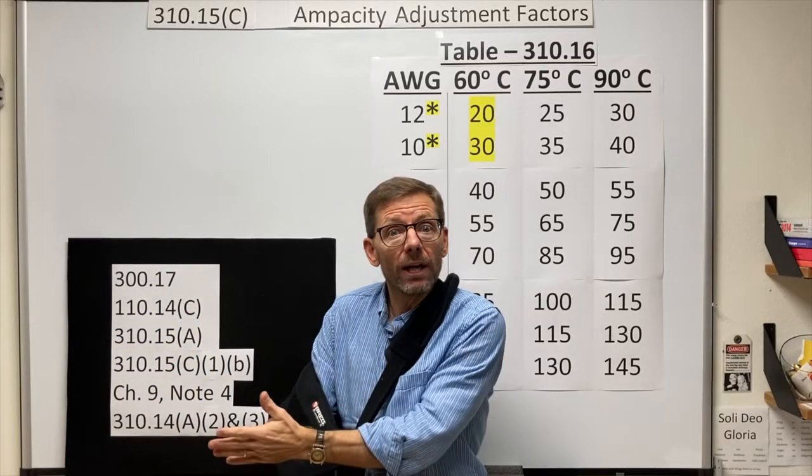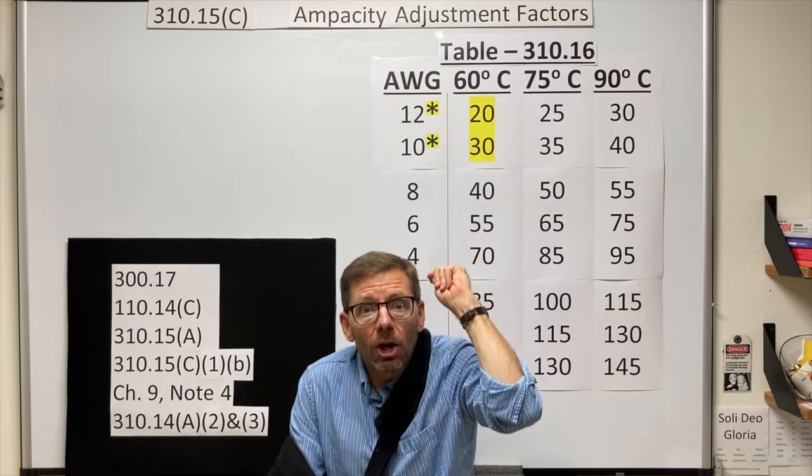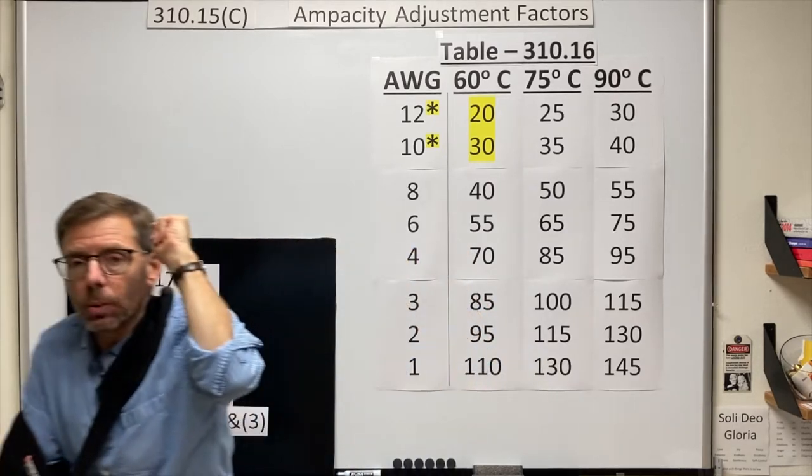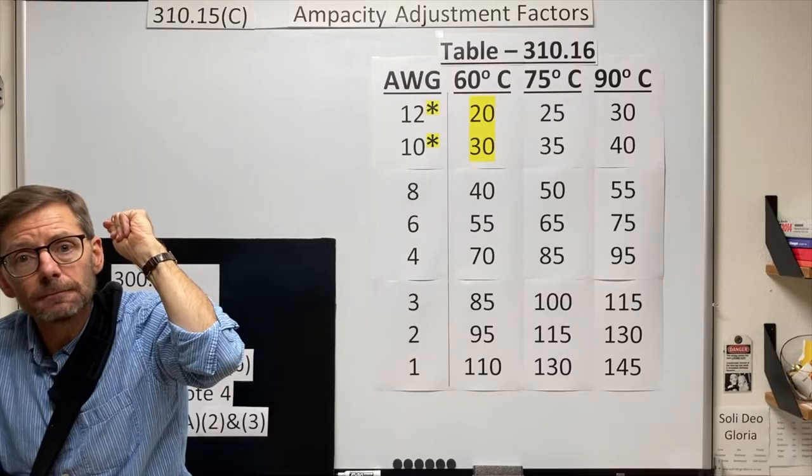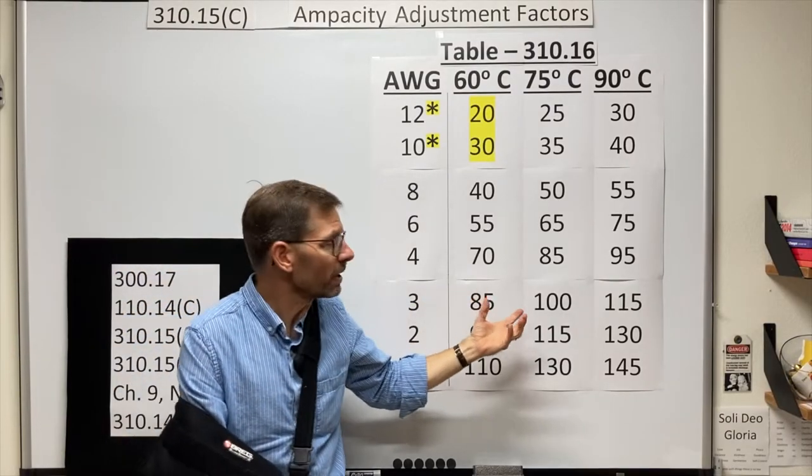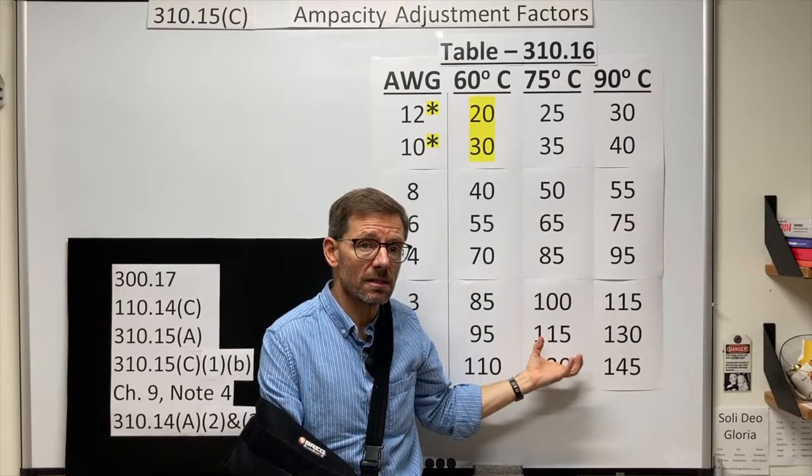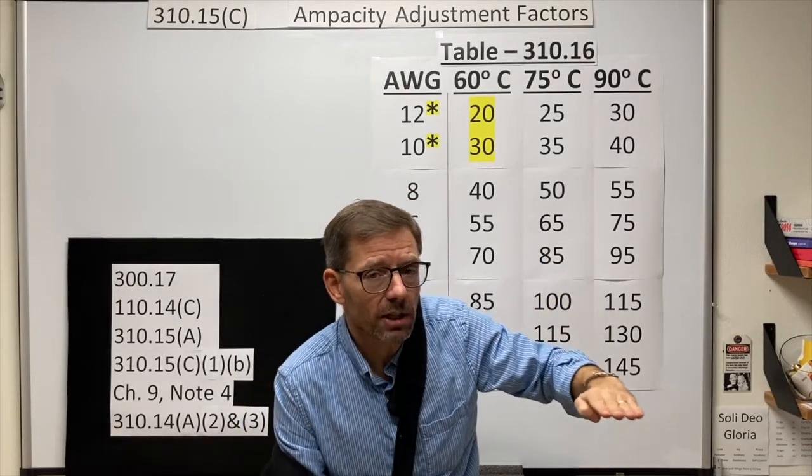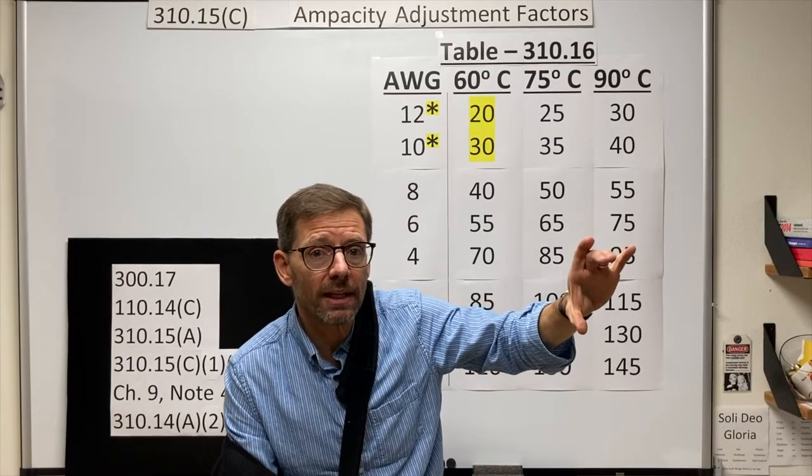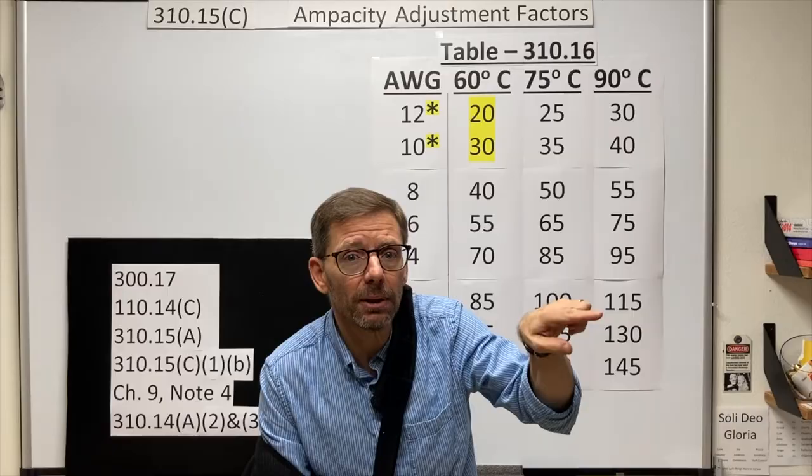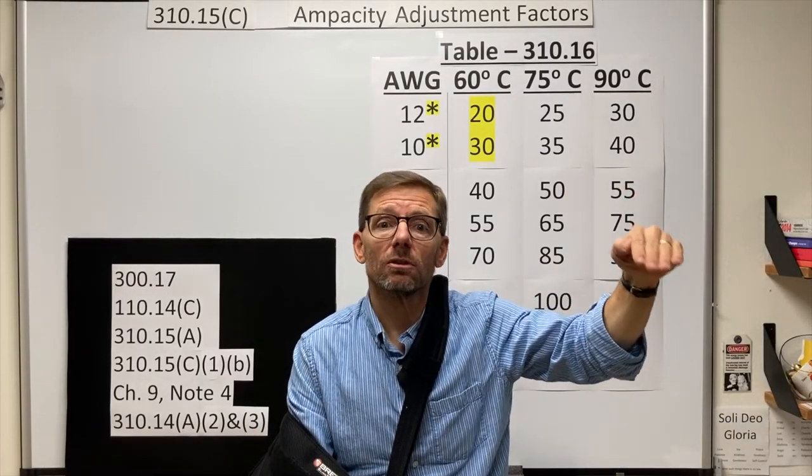Wouldn't it be nice if before we got on the train, we could all have a little ice pack, something that would lower our individual temperatures so when we get on the train we're all safe by the time we get to the destination? Conductors are similar. What we do is we restrict their ampacities so each conductor is starting off from a lower temperature. That way, when we put them in a raceway together, they still heat each other up a little bit, but not to the extent that they do damage to one another.